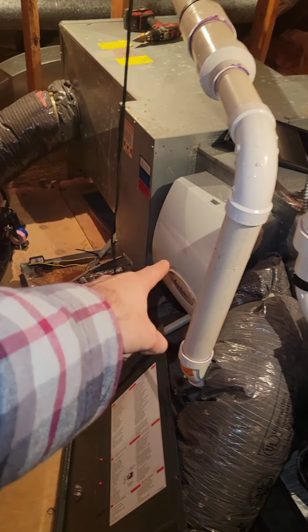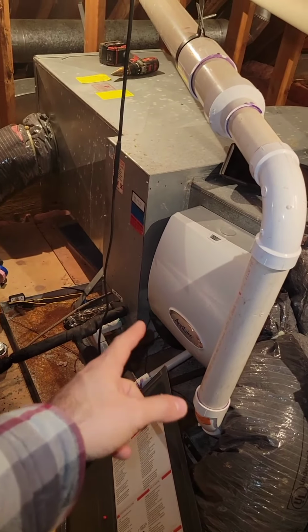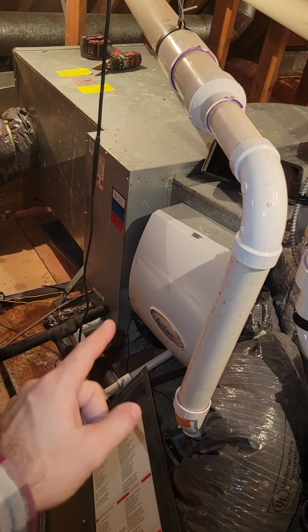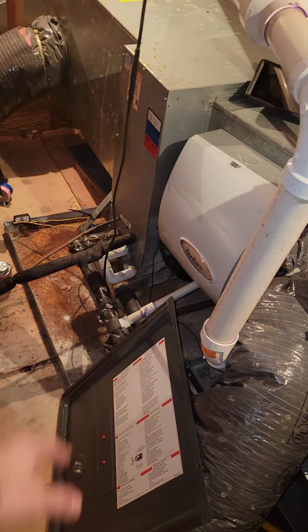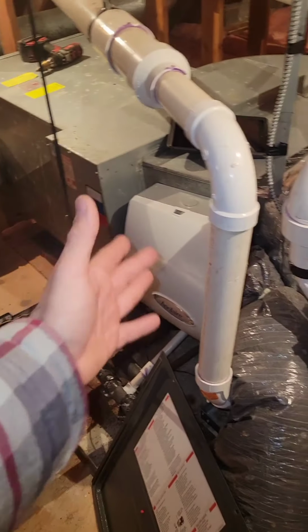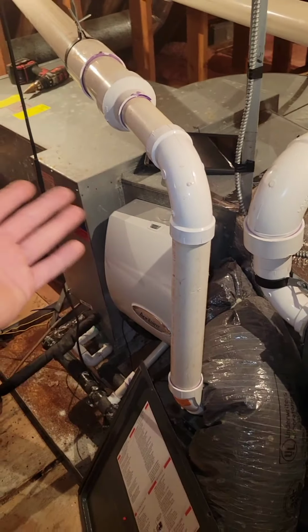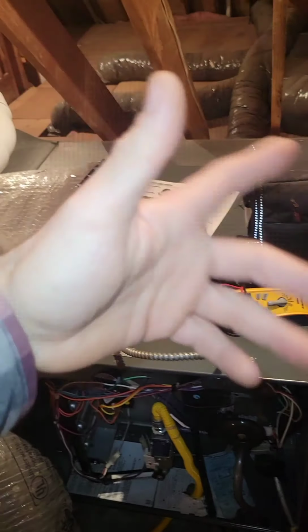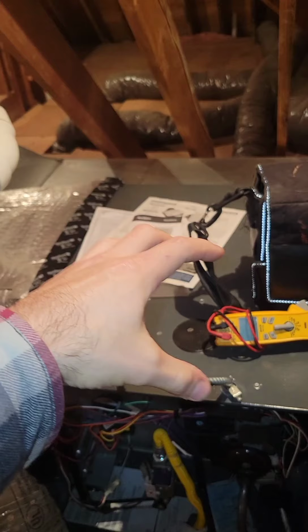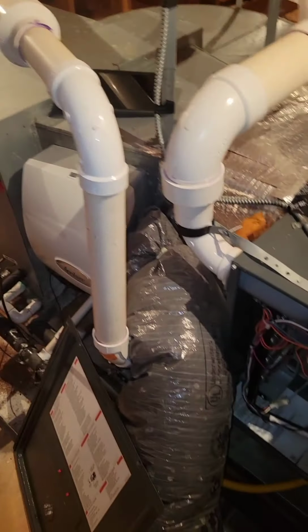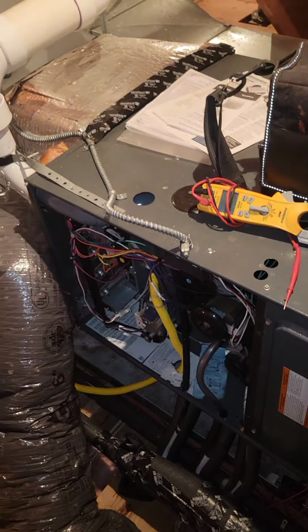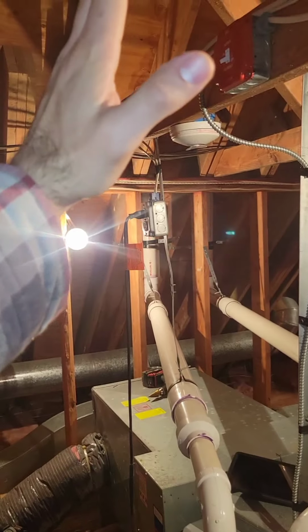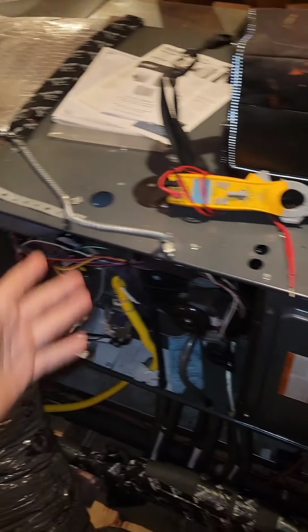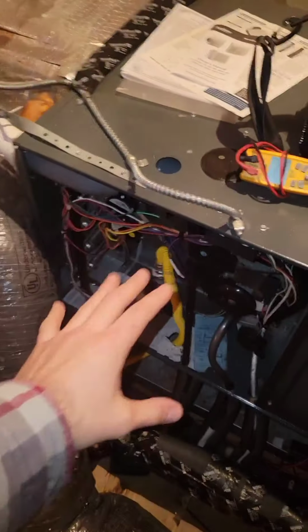Also, I don't like humidifiers up in the attic, and that one's actually been closed off. Customer told me it doesn't work for that particular reason, because it froze. The line froze down there. So obviously, again, no humidifiers in the attic. There's other ways to provide you with humidity, because your only option is to insulate this whole attic with spray foam or anything like that that will keep the space conditioned. Then you can have a 90% furnace and do whatever you want. Ideally you want an 80% here going right up the roof, and then that's it, because an 80% does not create condensation. But yeah, we gotta do a few more things here.